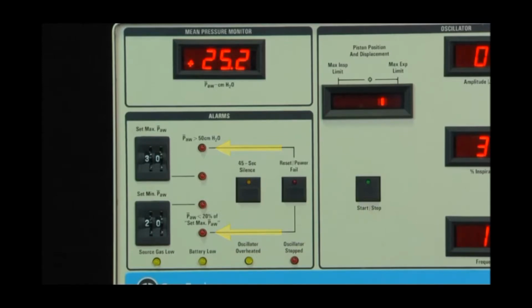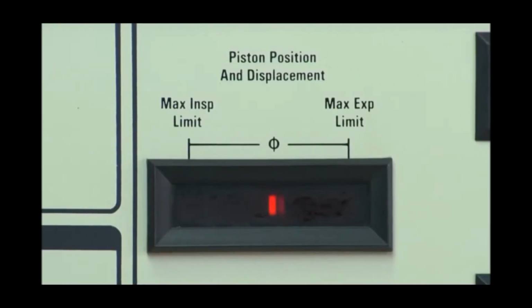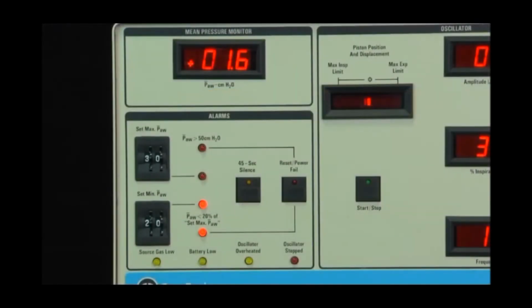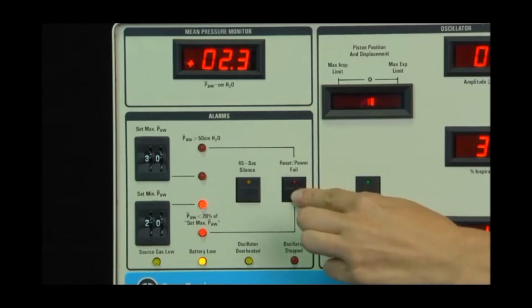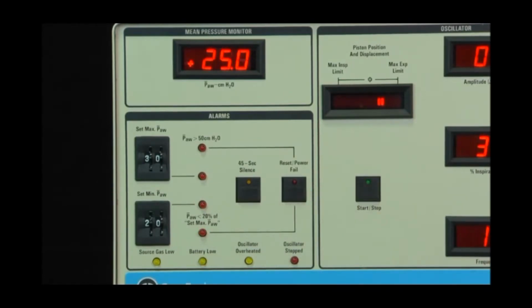These backup alarms are factory preset for greater than 50 centimeters of water pressure for the high alarm and less than 20% of the set high mean airway pressure for the low alarm. When these alarms are triggered, the oscillator will stop and the circuit pressures will be vented to ambient pressure. Bias flow will continue. Bias flow is maintained, allowing the patient the ability to breathe spontaneously at normal atmospheric pressure. Once an alarm condition has been resolved, the circuit must be repressurized manually by pressing and holding the Reset Power Fail button until the circuit pressure is at least 20% of the set high mean airway pressure alarm.